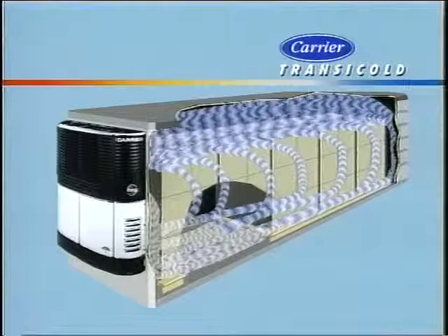You'll need to verify this portion of the test. If any portion of the keypad does not light up, there is a problem that needs to be brought to the attention of the shop supervisor. The unit will shut down for a few moments, and the microprocessor will then begin test number 2. At this point, the pre-trip will become automatic, and you can leave.